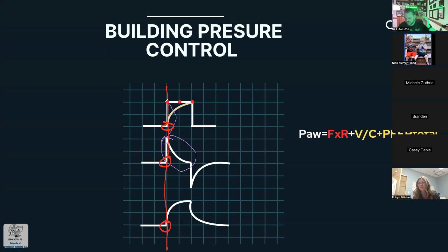In that split second that you've started inspiration, your airway pressure goes up to whatever you set. Your flow kicks on. Because the differential is very high, that flow is going to explode into the airway, right? So over time, as you deliver flow, your volume starts to go up. But because your volume is going up, the pressure inside the lung, which I have in yellow and beige, also starts to go up. As you raise the pressure in the lung, that delta pressure gets less and less, so your flow is going to go down and down because your pressure differential gets less and less. Therefore, your flow is going to go down over time because that differential is less.